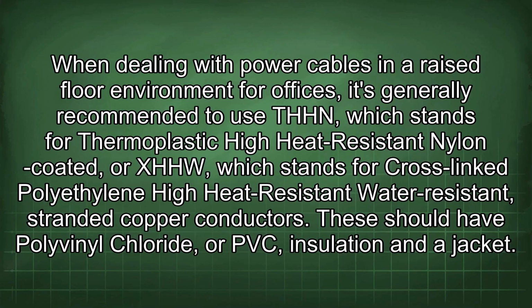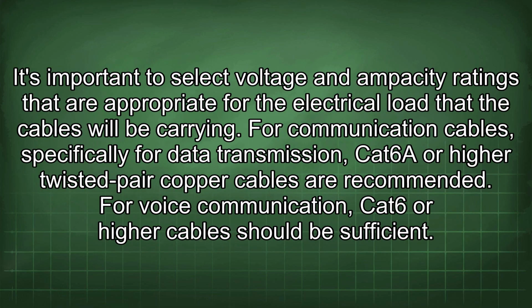When dealing with power cables in a raised floor environment for offices, it's generally recommended to use THHN, which stands for Thermoplastic High Heat Resistant Nylon Coated, or XHHW, which stands for Cross-Linked Polyethylene High Heat Resistant Water Resistant Stranded Copper Conductors. These should have polyvinyl chloride, or PVC, insulation and a jacket.